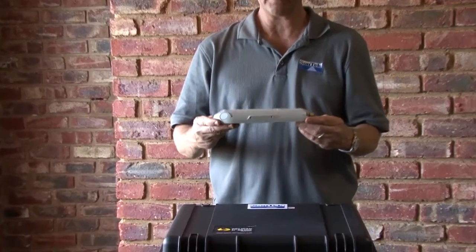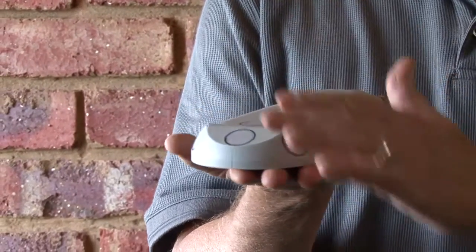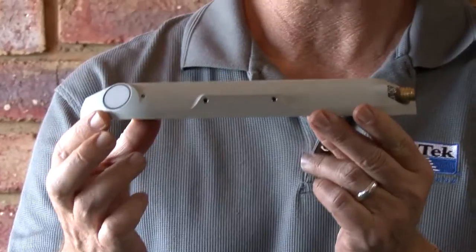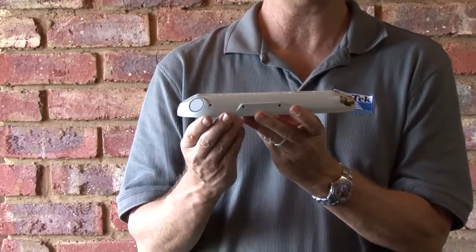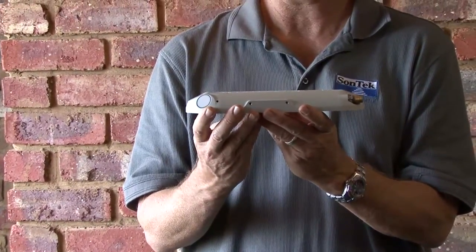As you can see, it's a very low profile. We've designed it this way to provide minimum drag in the bottom of the canal. That allows you to mount it much lower to the channel bottom, and also it disturbs less flow, so it allows you to measure accurately in much more shallow water than previous.